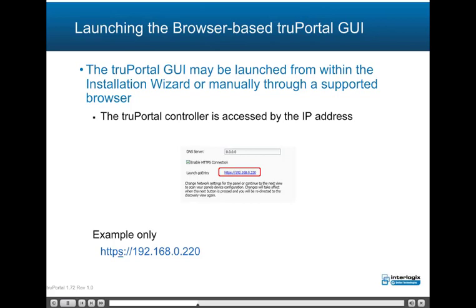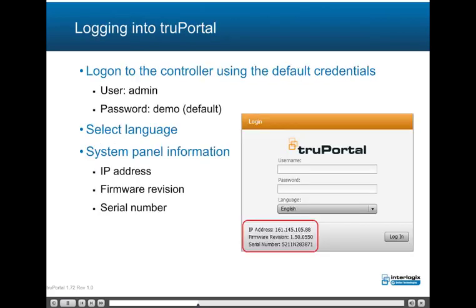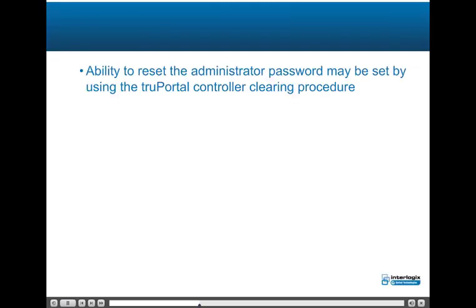The truPortal controller is accessed by the IP address configured for the system controller. The login dialog displays the system panel information including IP address, firmware revision, and serial number. The language may be selected based on what languages have been installed; the system defaults to English. Log into the controller using the first-time default credentials: user is 'admin', password is 'demo'. The administrator password may be reset to the default if forgotten by using the controller clearing procedure; contact support for the proper procedure.